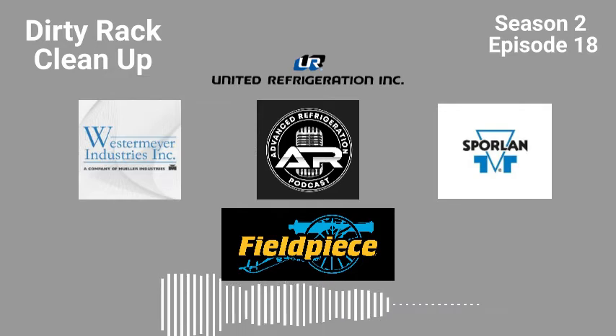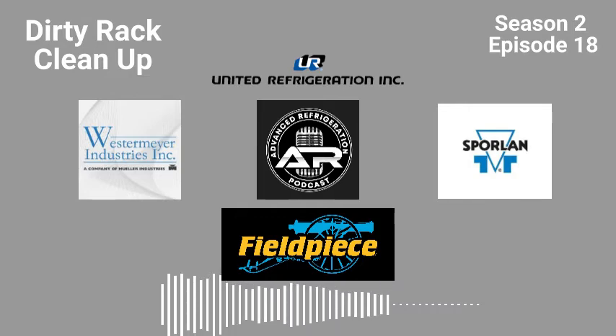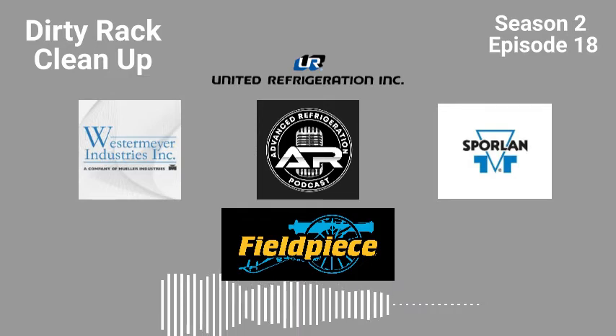Oh yeah, no, and I remember now. What are you doing when you have an excessive amount of wax going through the system from, let's just say, the condenser on? What's your fix for that? You're not going to pump down the whole system and blow a ton of RX-11 flush in there. What are you going to do? The only thing you do is throw in wax dryers. That's the only thing I've seen.